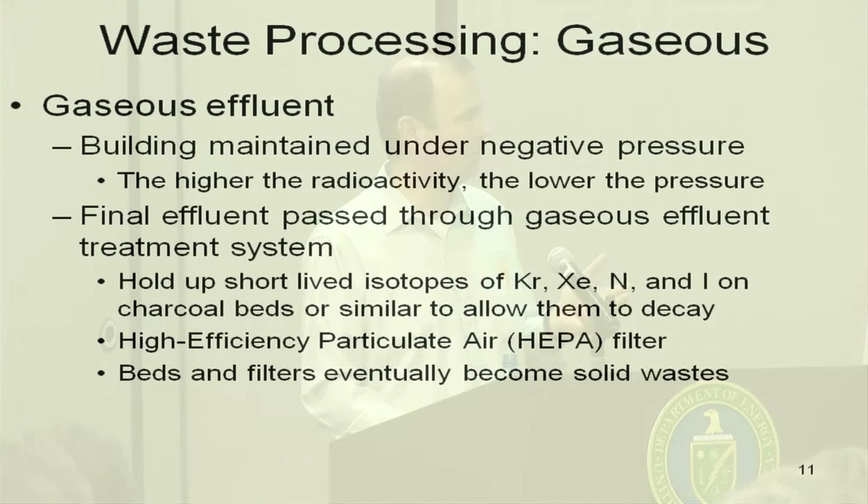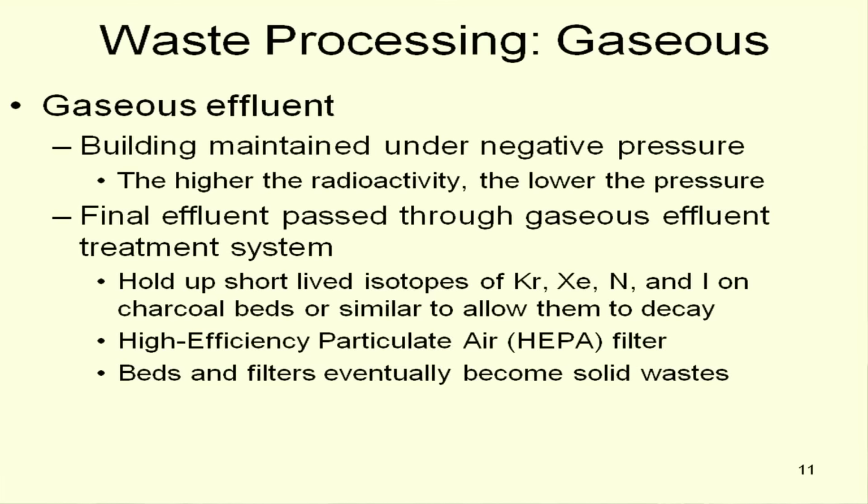And what you do is you run that through something like a charcoal bed. These isotopes tend to be quite short-lived, and the charcoal bed just sort of holds them up for long enough so they decay away. Then the resulting gas stream keeps on going through a high-efficiency filter, and then it goes out of stack. But eventually the charcoal beds and filters become solid waste. And again, they get put in barrels and treated like a low-level waste.